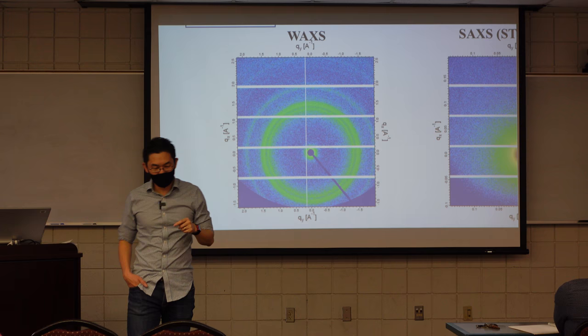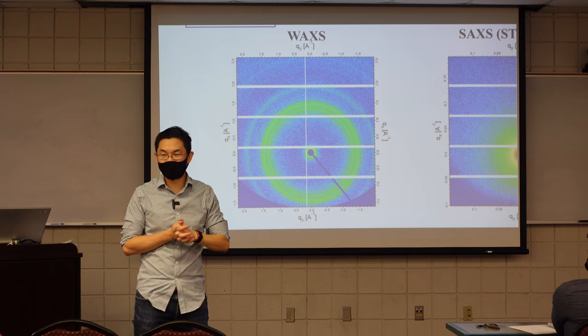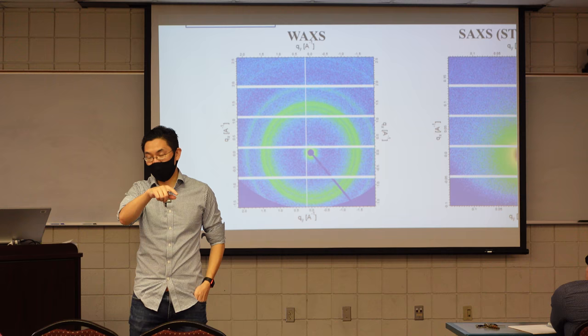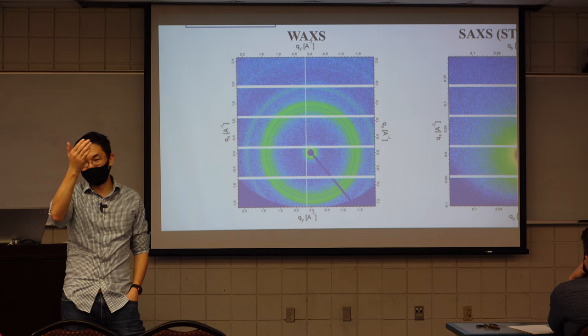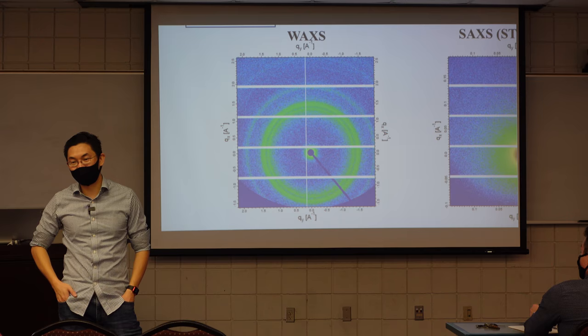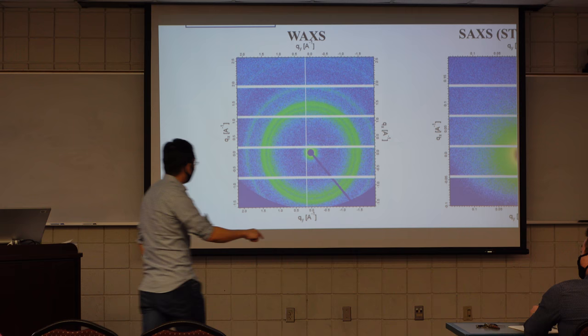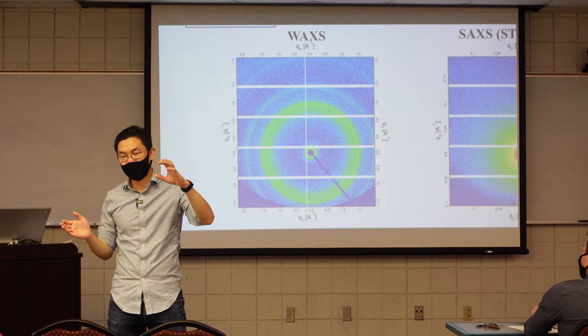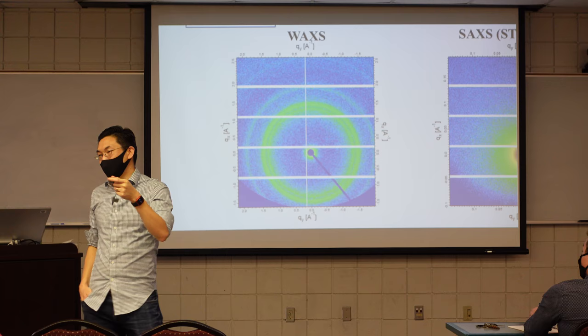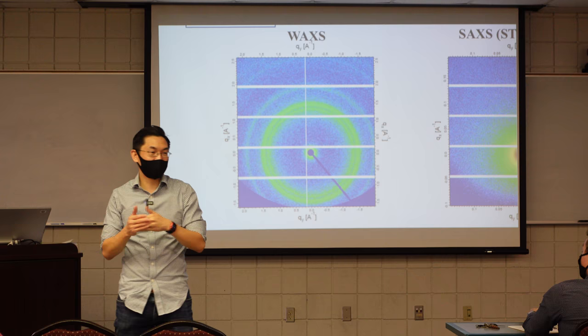There are two reasons we need this. First, in our case, we don't want the beam to pass through the back Kapton window. Remember, as I mentioned, there's a gap between the flight tube and the vacuum to the detector. We have a Kapton backed by a Kevlar material, so it can sustain the vacuum. But that thing also scatters, so we need to block the beam before it exits. That's where this thing comes in. It's circular in shape. It's basically a piece of metal mounted by small rods. I'll show everybody when we're in the lab. And that piece of metal is fairly thick, about 2-3 millimeters thick, and that can attenuate any X-ray totally. So no X-ray can pass it. And that's how it looks like this, okay?